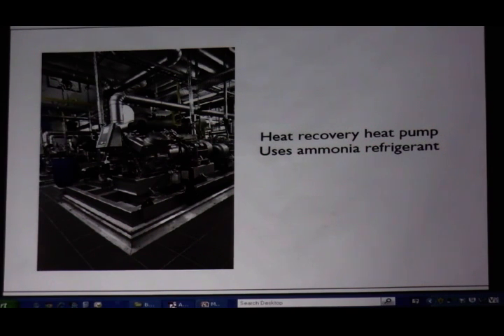And ammonia is a high pressure refrigerant to use as a heat pump. Right now, the gas compressors can only give you about 100 degrees centigrade, 210 or 212 degrees Fahrenheit. And that's what this is doing. This is the kind of compressor they use.